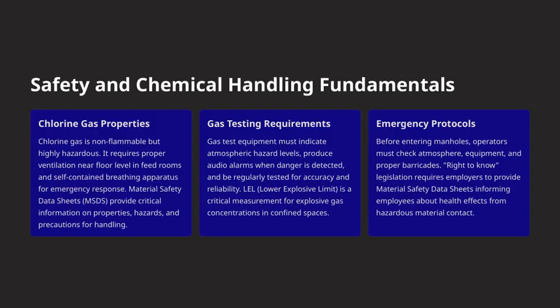Let's talk about safety and chemical handling fundamentals, starting with chlorine gas properties. Chlorine gas is non-flammable, which is good to know, but it is highly hazardous. That means we need to be very careful when handling it. Proper ventilation is essential, especially near the floor level in feed rooms, because chlorine is heavier than air and tends to settle low. In case of an emergency, using self-contained breathing apparatus is critical to protect ourselves. Also, material safety data sheets, or MSDS, are our go-to sources for vital information. They detail the properties of chlorine, the hazards involved, and the precautions we should take during handling.